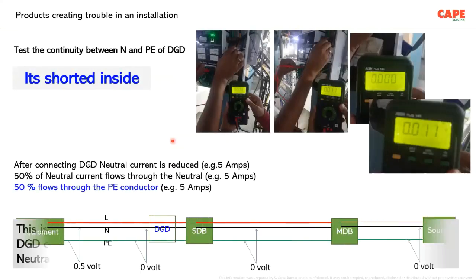Actually, what happens is that internally, these companies are shorting the neutral and the earth. By making a short circuit between the neutral and the earth, the potential difference between neutral and earth has been made zero. But this equipment will create a lot of problems. The neutral current, the partial neutral current, will flow all over your electrical installation. And this device is going to create a fire in other circuits, not in the connected circuit of this particular device. Probably the connected circuit of this device doesn't have any problem, but other circuits are going to have serious issues of failures and fire.